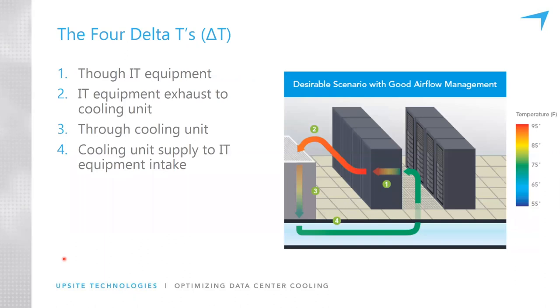So another very valuable way to understand cooling optimization is to look at the 4 delta T's in the room. There are 4 delta T's in the airflow path as it moves through a room. Now, most people will really be focused on one or the other. The IT people, of course, are focused on the amount of temperature change as air moves through the IT equipment. Mechanical people are really focused on how much the air temperature drops as it moves through the cooling units. But there are 2 other delta T's that are very important. That's how much the air heats up from the time it leaves a cooling unit before it goes into the warmest intake, and how much the air cools off from the time it leaves an exhaust from an IT equipment before returning to a cooling unit.